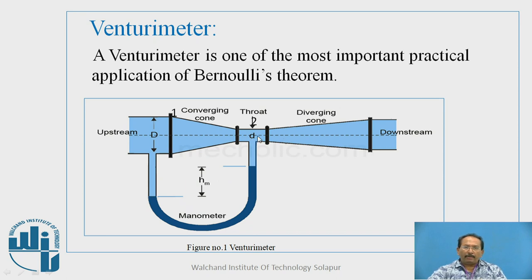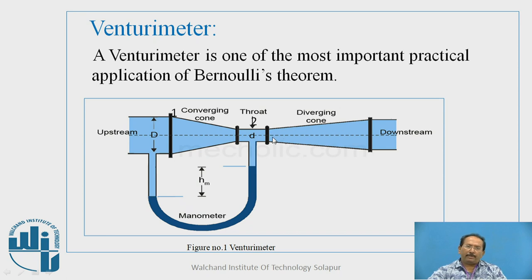One more thing you can observe in this figure: this particular length of the diverging cone is more — why? To avoid cavitation. As the cross-section is reduced, the velocity will be more and liquid can pass very fast, so there are chances of cavitation. That is why the length of the diverging cone is always more than the convergent cone.